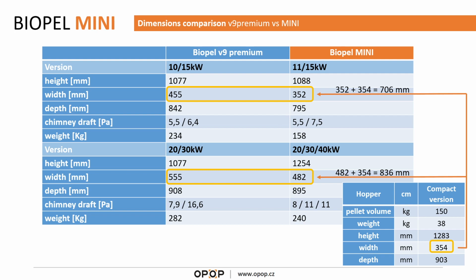Now let's compare Biopel Mini and Biopel V9 Premium to see the differences. We will start with dimensions. In this slide you see the Biopel V9 Premium column and the Biopel Mini column. Okay, and we have different powers. So this is the standard V9 Premium 10-15 kilowatt, 20-30 kilowatt, and here the same type of boiler but Biopel Mini with powers 11, 15 and 20, 30, 40 kilowatt.